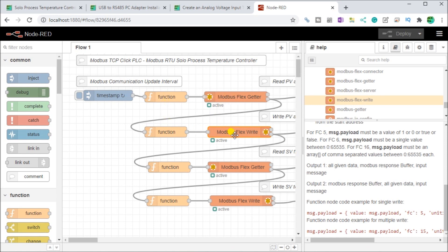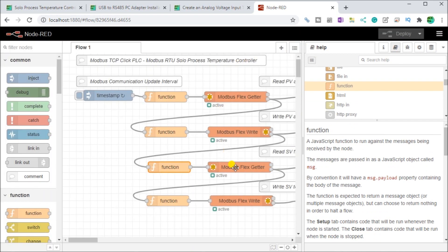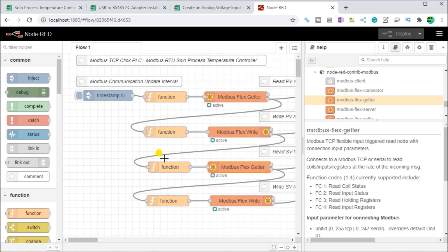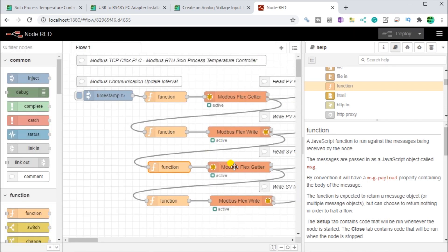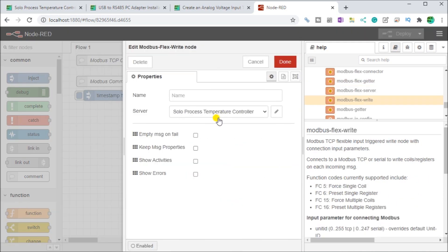Next, we read from the Click PLC the set value to write back to the Solo. A function block sets up the parameters, and the flex getter reads from the Click at address 2 — that's the third register (zero, one, two). Once that value is read, we write it back to the Solo using address 4097, using a flex write node directed back to the Solo process temperature controller.